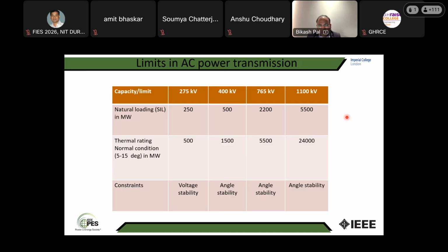Now when the conductor is heating up, that end would expand, and the annealing temperature of aluminum, reached at 130 degrees Celsius, is the limit. That is the limit beyond which you cannot carry current, because at that point the conductivity of that transmission conductor would permanently change. That is called the thermal limit. So now in reality, are we able to reach the thermal limit? We can reach or exploit the thermal limit depending on the length of the line. If the line is less than 50 miles, then reaching that thermal capacity is possible.